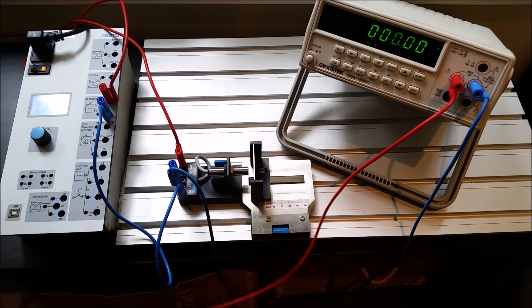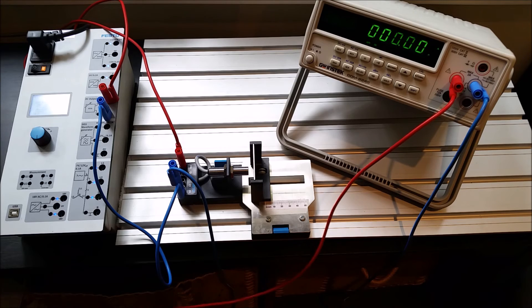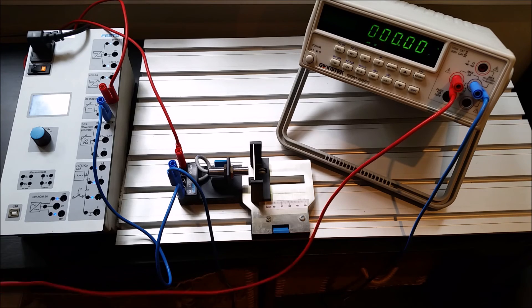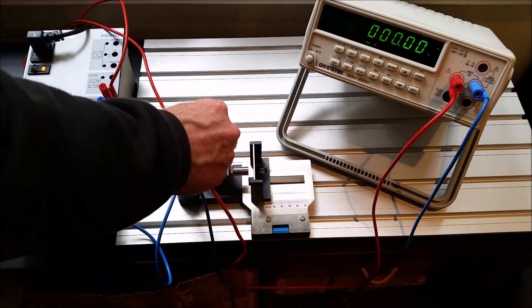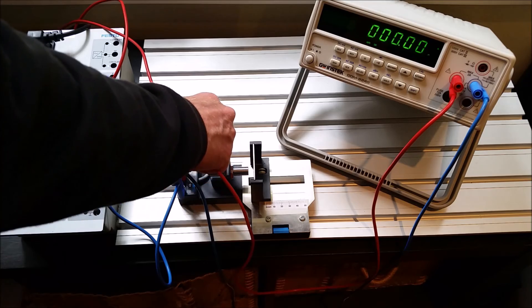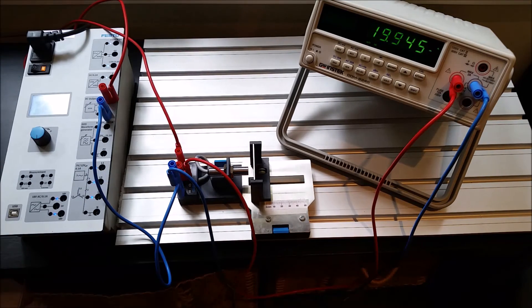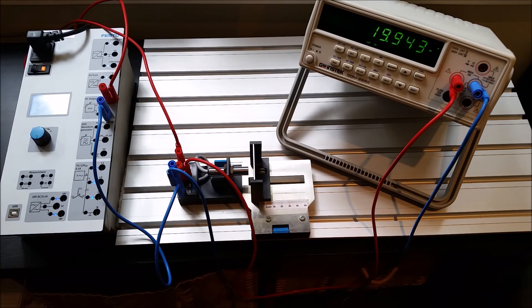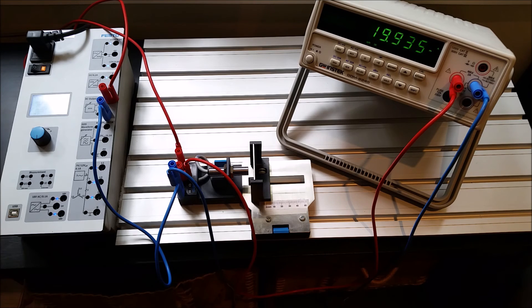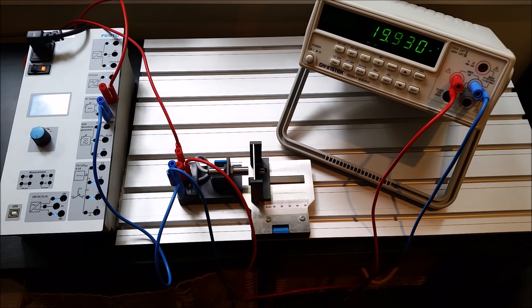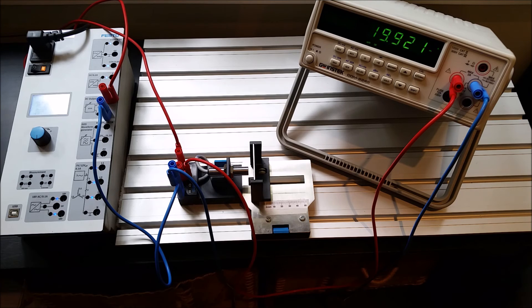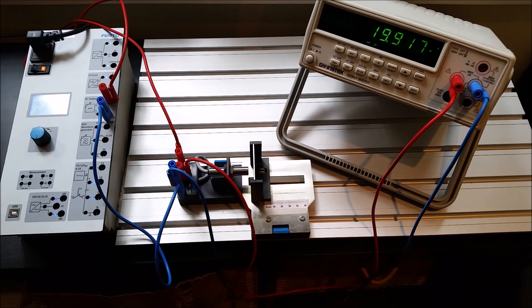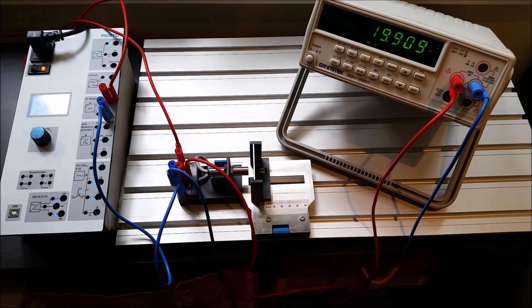And now the output for current is off of a different terminal. From that lab, you can see that Q2 is the output for current. And as it comes in, you can see that it auto ranges and went from microamps to milliamps. Be careful. Make sure that you put it in the right setting. Have the wire from the sensor from Q2 going into the 200 milliamp probe opening. And don't change meter settings while it's live. Otherwise, you're going to smoke the fuse.